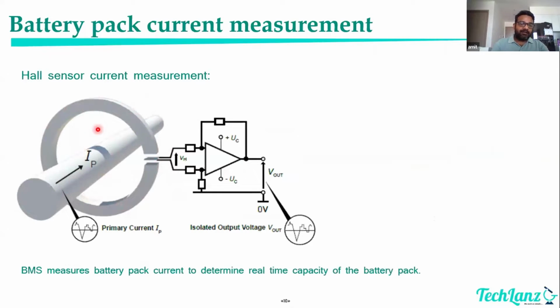How does this measure current? Recall the right hand thumb rule from school. If current in the bus bar flows in a certain direction, it generates a magnetic field proportional to the current flowing in the conductor. That circulating magnetic field interacts with a silicon device kept inside the sensor, which generates a voltage proportional to the magnetic field generated in the Hall effect sensor. That voltage gets amplified, and the BMS reads it to determine how much current is flowing through the conductor.